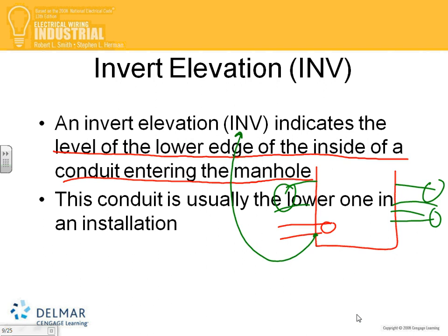So that elevation, let's say 735 feet, has to do probably with the water, guys. These manholes, you need to know how low this point is, because at a certain time it could be below the water table, and the conduit becomes a water conduit.